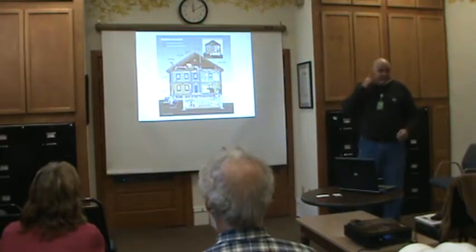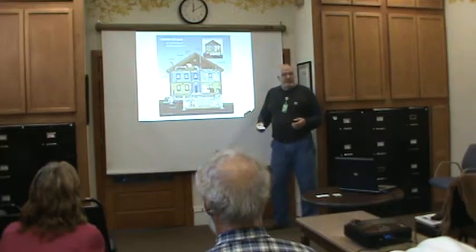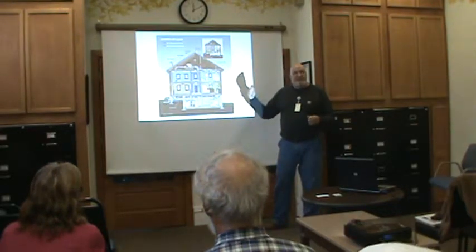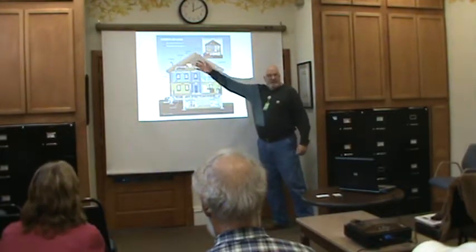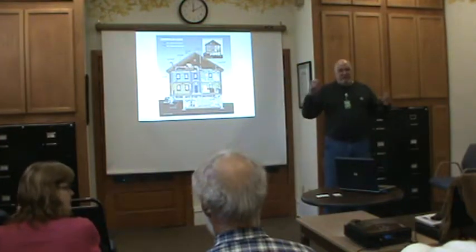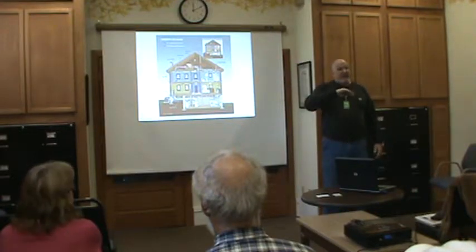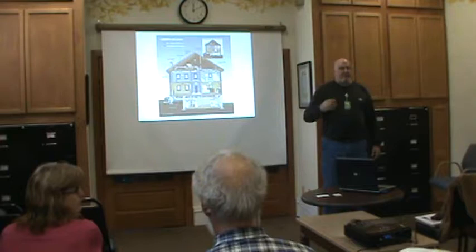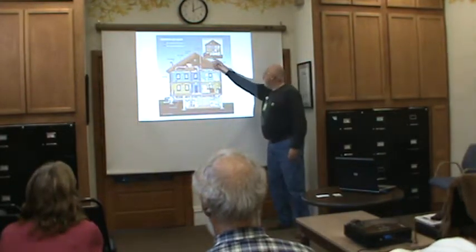There's something called the stack effect. So if you imagine it in winter, the hot air rises, right? It's usually a little harder to cool the second floor than it is to heat it. So that hot air is finding all the cracks and crevices at the attic hatch, at any other sort of orifice. If you've got a whole house fan in the attic and it's not well sealed, insulated, and capped off in the winter, it's just like having a big hole in your roof practically. So these are places air leaks out.